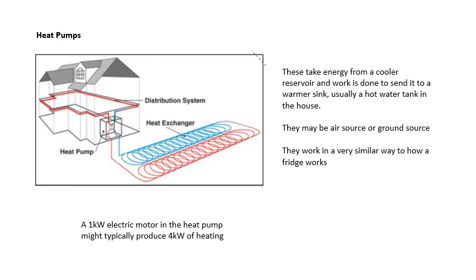One advantage of them is that in the summer they can actually be used as air conditioning to keep the house cool if it gets a bit too warm. They work in a very similar way to how a fridge works. The clever thing is you've got an electric motor which might be, say, one kilowatt, and you're typically getting something like four kilowatts of heating. So in that sense it's about 400% efficient.